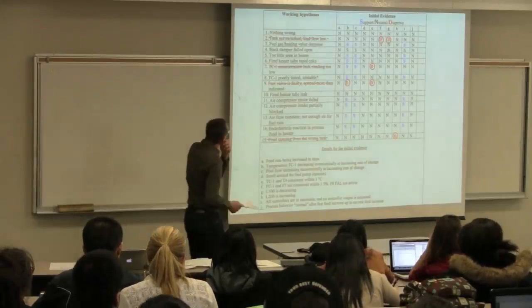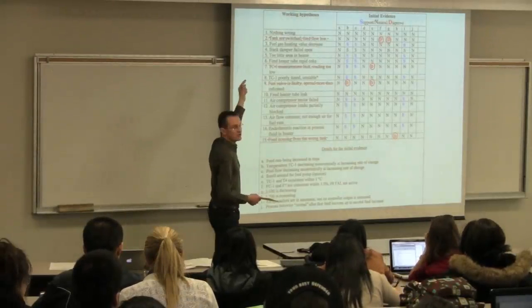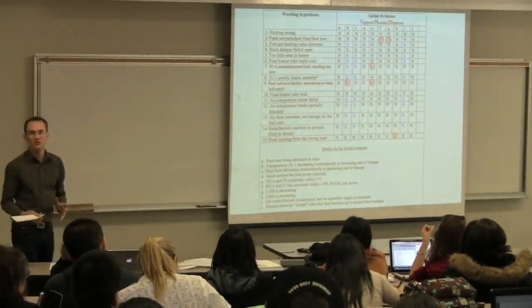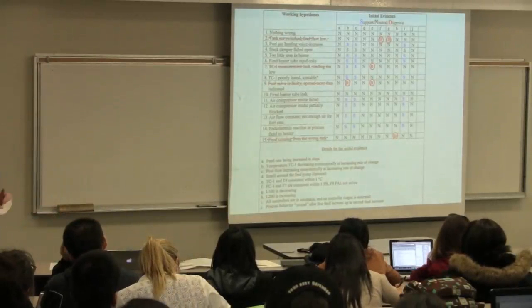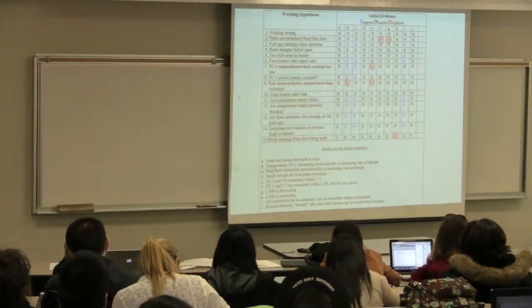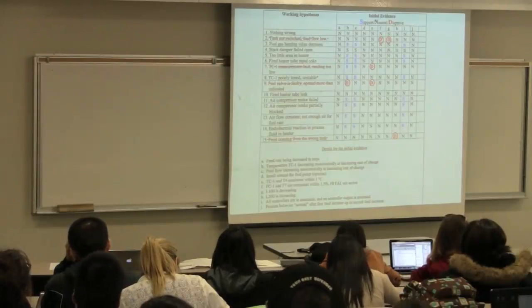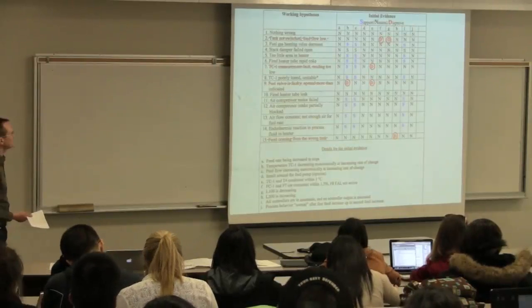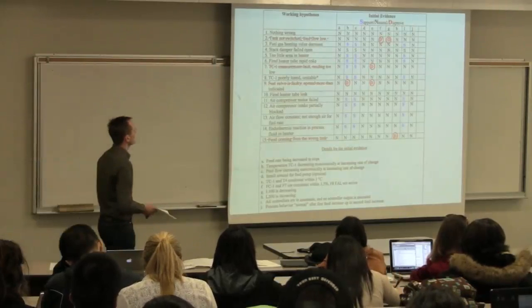The first step, you might say, and it's always valid to start with your first hypothesis, is to say, well, nothing is wrong. All I'm observing in those trends is just temporary behavior, and the feedback control system is going to sort it out. It's just a transient blip or duration where I'm expecting some deviation. That could be your first hypothesis.